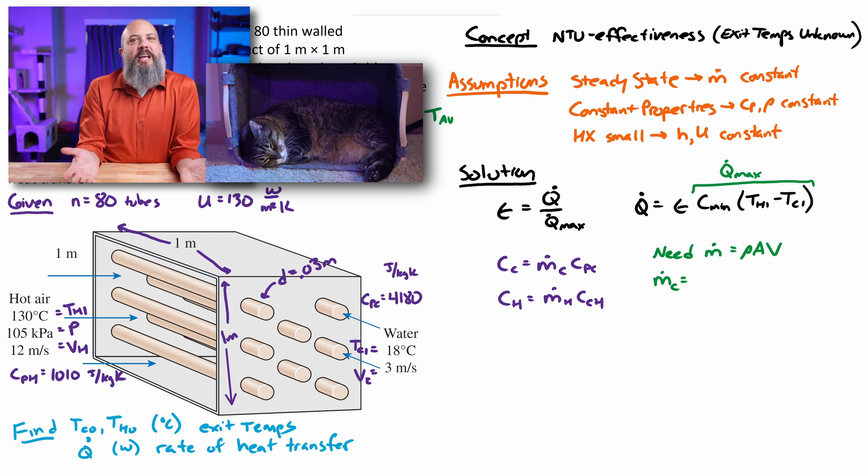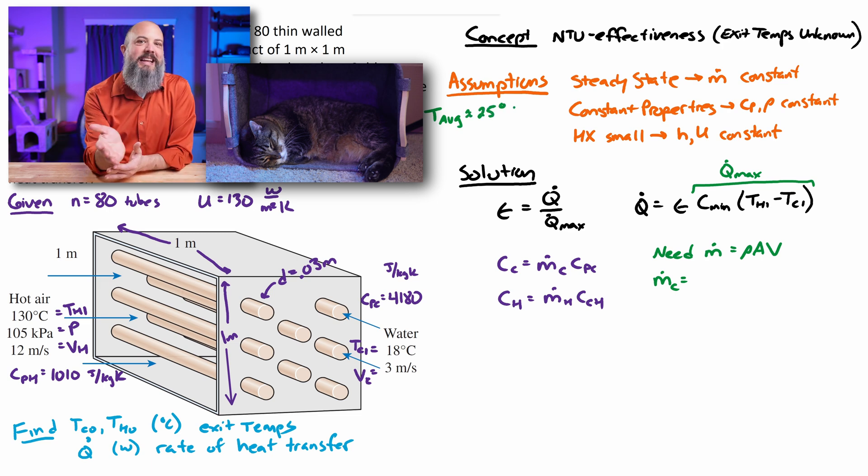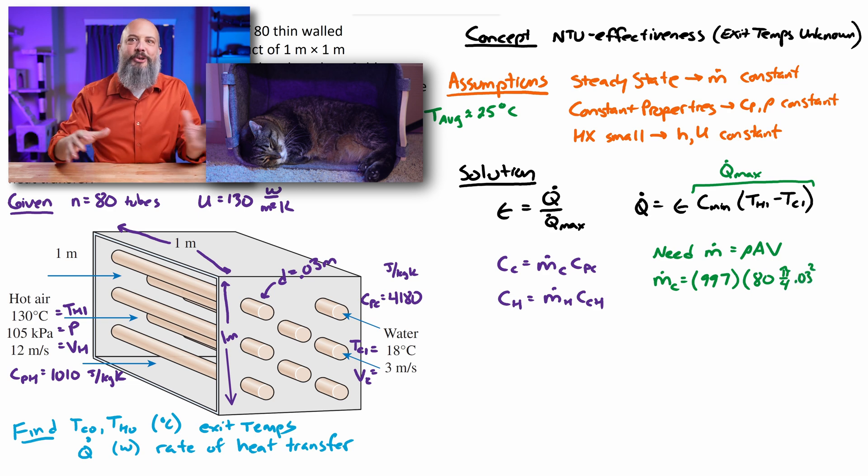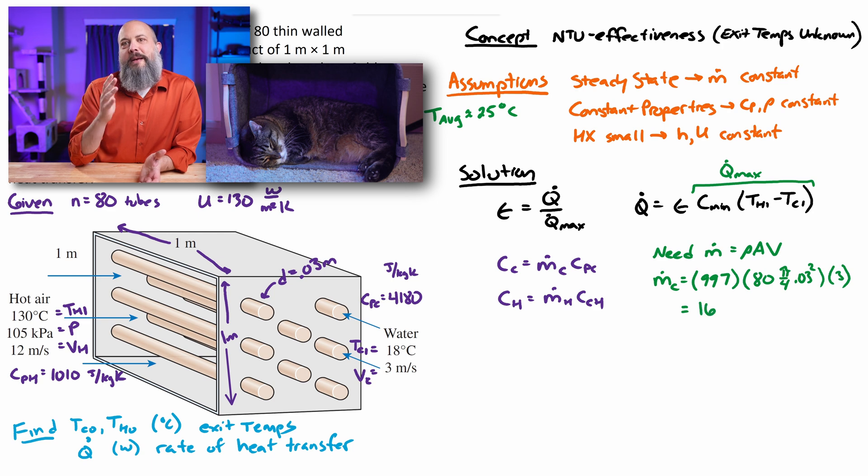And I'm just going to go ahead and make a guess here for the density because we don't actually know what the outlet temperature is going to be. I'm just kind of guessing that we'll get 997 for density, right? I'm assuming an average temperature of 25 degrees Celsius, like maybe it's coming in at 18 and leaving around 30 and averaging around 25. So I'm going to grab density at 25 Celsius of 997. But that's something we'll have to check at the end to see if that was actually a good guess. So cross sectional area, we were given a diameter for each pipe of 0.03. So pi over 4 times diameter squared. But then we also have 80, 80 tubes. So 80 times the diameter of each tube gives us cross sectional area. And the velocity we were also given 3 meters per second. This gives us a mass flow rate for the cold flow of 169.1 kilograms per second.